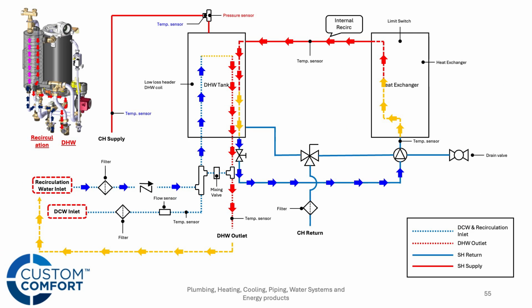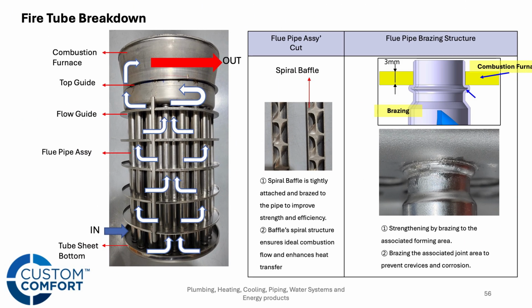And this is just a look at the domestic recirc mode as well. So again, using domestic, we can keep that buffer tank hot so that there's hot water available at all faucets throughout the house. It's a cool look at the inside of that fire tube heat exchanger, right? Just took the hood up. Now we're looking inside the engine and the workhorse of this boiler. There's 76 of those spiral baffles that go through the fire tube heat exchanger. It's got nickel brazing to prevent any leaks down the road on that heat exchanger.